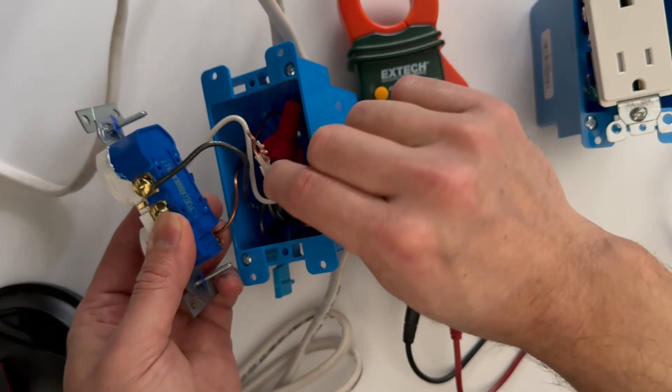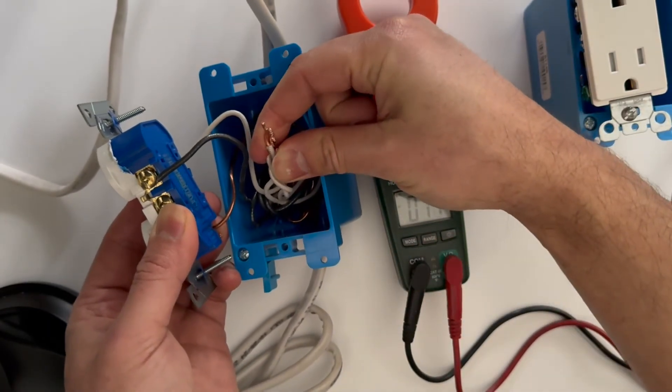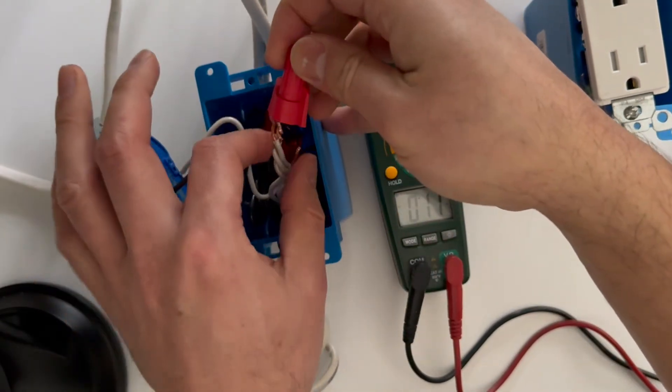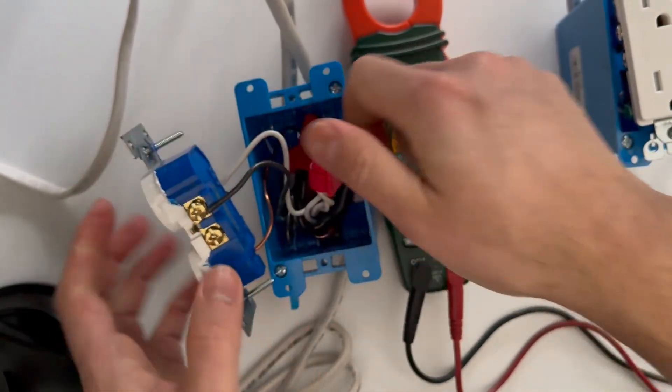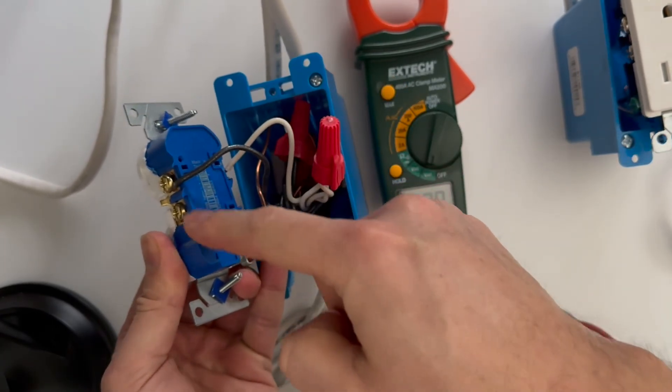For the most part, your job is to locate the problem visually because this is where wirings fail - where you have multiple connections in the junction box, whether it's being made with pigtailing like this.